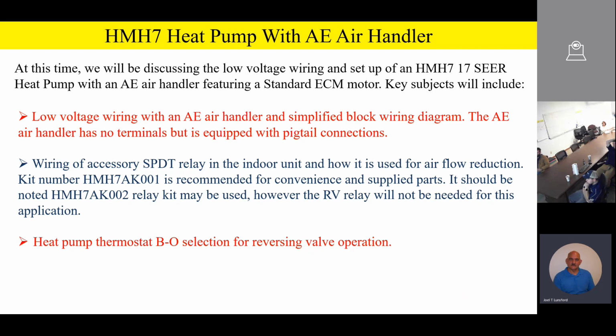And we also want to make sure that when we reduce the airflow, that reduced airflow needs to be about 60% of our full airflow. So again, we set it up for 400 CFM per ton on the high-speed cooling airflow, and then 60% of that for our reduced airflow command. And we're going to do all that by utilizing a single pole double throw relay in the indoor unit. And we're going to recommend kit number HMH7AK001 for convenience and supplied parts.